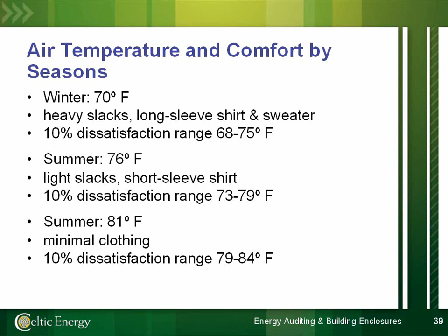That's one of the things we find as auditors as notoriously difficult to nail down, is what those set points really are and how they're changed. In big offices, if occupants have access to thermostats, there's all kinds of games and turf wars over who controls the thermostat. I've seen lock boxes put over thermostats, with people trying to defeat them with a bag of frozen peas or a lighter underneath, and all kinds of things. A lot of it has to do with the lack of proper building enclosure technology and maintenance, from how the building was designed and built to how it's been maintained over time. So it directly affects what you guys are involved in every day.